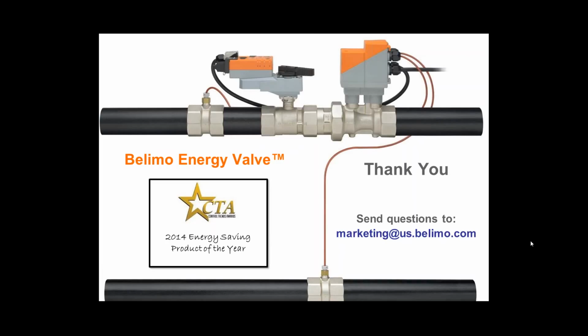Okay, we'll take this last question. If you improve your delta T from 6 degree to 12 degree Fahrenheit, what return on investment could I expect if I was replacing a 12-inch chilled water valve, not including labor to install the valve? What is the general return on investment you see? Is it cost effective? Well, I can't answer your question exactly, but I'll give it a swing. If you change your delta T from 6 to 12, you're cutting your flow in half. If you cut your flow in half and you apply pump affinity law, it means you're cutting your pumping costs to that particular place by 7/8.